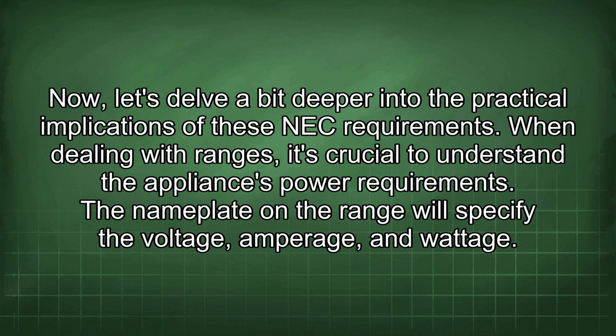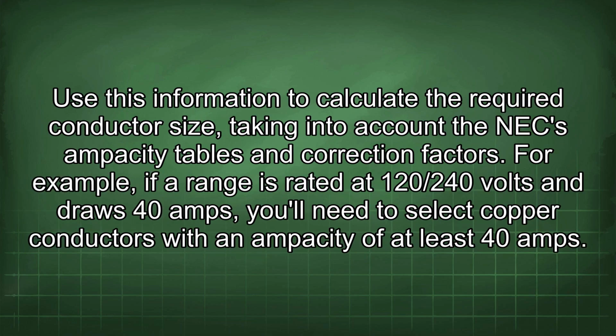When dealing with ranges, it's crucial to understand the appliance's power requirements. The nameplate on the range will specify the voltage, amperage, and wattage. Use this information to calculate the required conductor size, taking into account the NEC ampacity tables and correction factors. For example, if a range is rated at 120/240 volts and draws 40 amps, you'll need to select copper conductors with an ampacity of at least 40 amps.